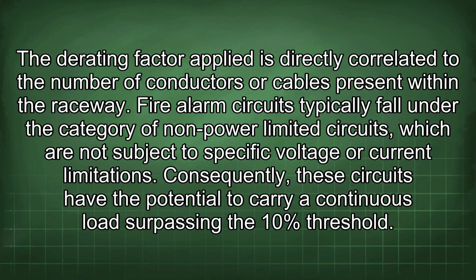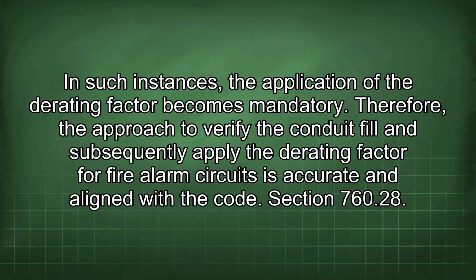Fire alarm circuits typically fall under the category of non-power limited circuits, which are not subject to specific voltage or current limitations. Consequently, these circuits have the potential to carry a continuous load surpassing the 10% threshold. In such instances, the application of the derating factor becomes mandatory. Therefore, the approach to verify the conduit fill and subsequently apply the derating factor for fire alarm circuits is accurate and aligned with the code.